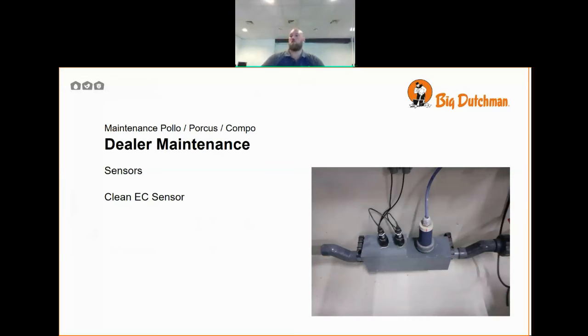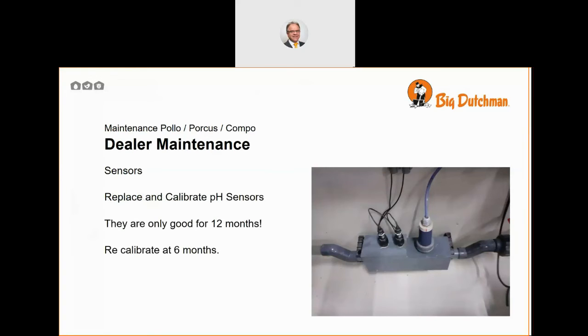value is rising correctly. I have one question. Sorry, the pH sensors have to be physically replaced with a new one at 12 months? Yes, at 12 months. Okay, and the calibration is done on the PCB board or inside the software? With new systems, we have a software-based calibration program, so you won't need to do anything on the printed circuit boards. On older systems, we used to have a method of doing this through the parameter input screen with the old digital readout screen, like a digital clock, and scrolling through the parameters and changing the parameters 1 to 0. Okay.